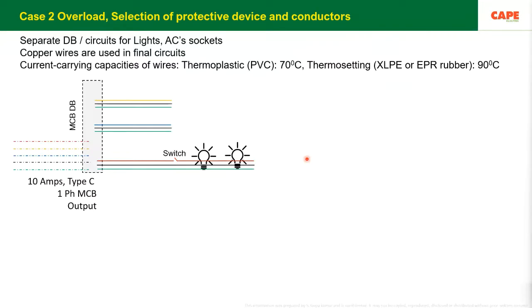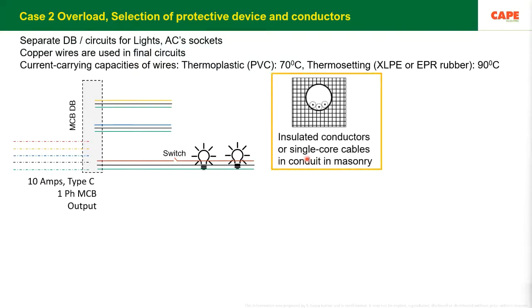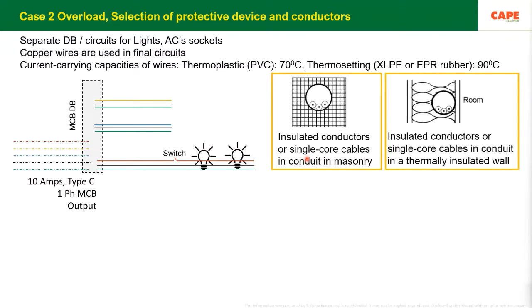So instead of saying an accident is due to an overload, we should start saying that the accident is due to non-disconnection of a protective device, or non-operation of a protective device. We have to change the term a little bit. Only if we start calling this a non-operation of a protective device will people start realizing the seriousness of selecting the appropriate device and putting it into the circuit.